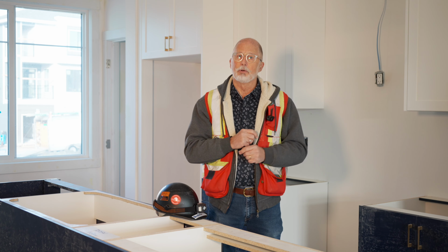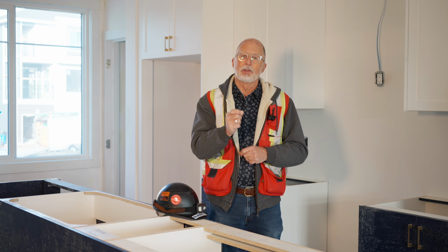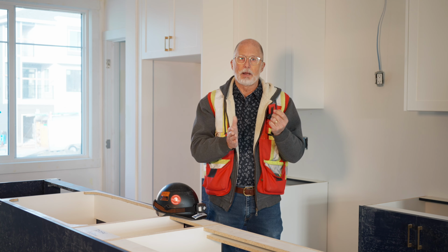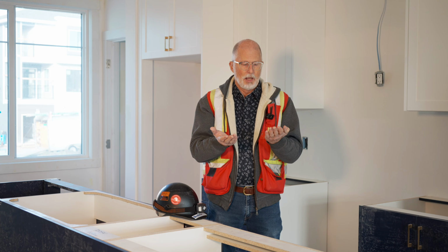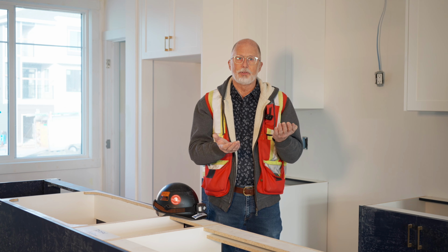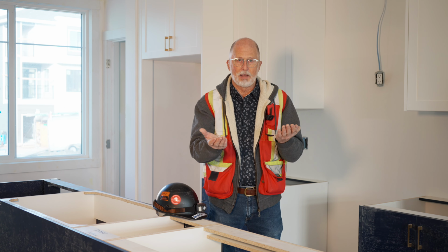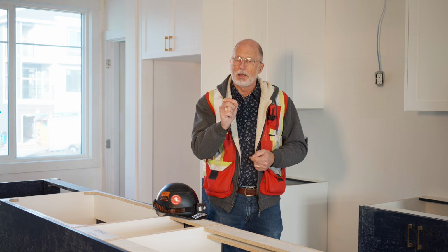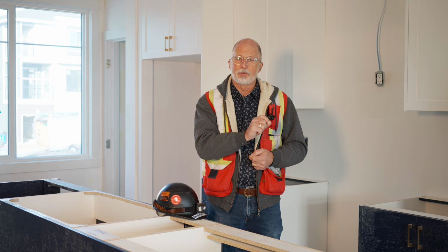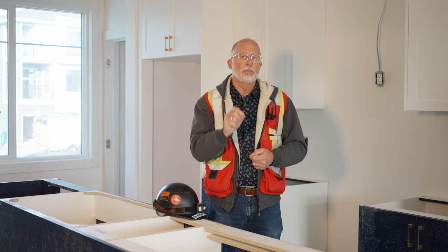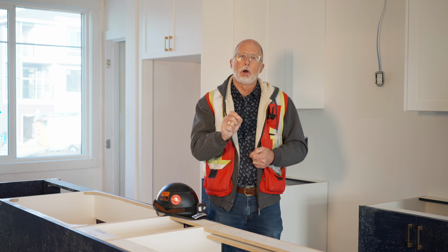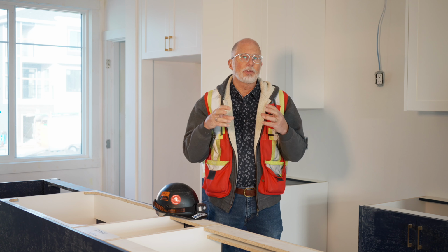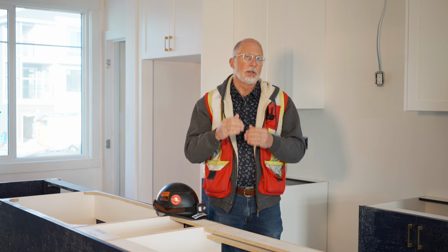So that can influence, if you have a neighbor that's on an end unit and then the neighbor on the first inner unit compare their EnerGuide ratings and they go, well, how come I've got 2.5 ACH and you've got 3.5 ACH? We did the construction the exact same way, but because the end unit has less party wall, it's going to be more airtight. So that's why it's difficult to do multifamily, get the airtightness down where you want it to be the equivalent.